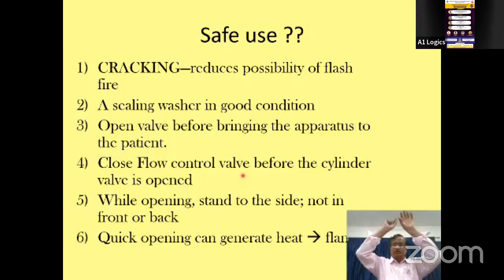Check that the sealing washer is in good condition. Open the valve before bringing the apparatus to the patient, and close the flow control valve before the cylinder valve is opened. I have seen that when the cylinder is full at high pressure, if you open the oxygen suddenly, the flow control valve can shoot up and stick to the top, and it will not come back down.